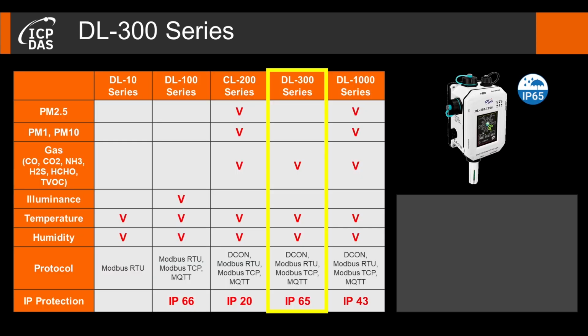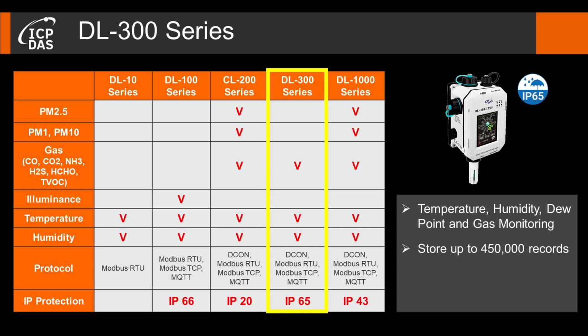The DL300 series data loggers also support various protocols such as DCON, Modbus RTU, Modbus TCP, and MQTT protocols, and can collect the data on temperature, humidity, dew point, and gases with the date and timestamps included, and can store up to 450,000 records. In addition, DL300 series has the LCD display to show the real-time data. And DL300 series can also integrate with iAir utility. The management personnel can download the Air application on mobile phones to retrieve real-time data monitored by DL300 series anytime and send messages to the LCD built on the modules.